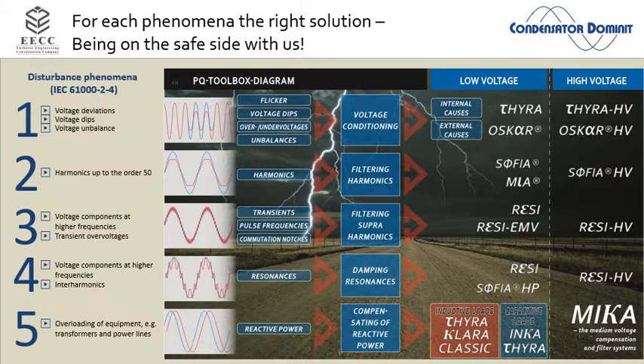In the standards there are certain phenomena of power quality, which fall under one category: voltage deviation, voltage dips, voltage unbalance, flicker, over and under voltages. All of these have one thing in common, we're talking about the RMS voltage, it's too high, too low, unbalanced, changing too fast, or changing over the day.